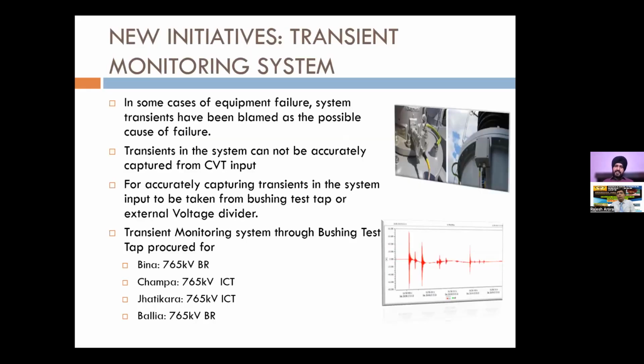Now, when we talk about initiatives in Power Grid, like I said, the high frequency transients are very much relevant. To monitor these transients, we have captured, and because these transients cannot be accurately measured through a CVT, because CVT is attuned for maximum accuracy of measurement at 50 hertz. So we have got this transient monitoring systems which are monitoring the system transients directly from bushing. Bushing basically acts as a voltage divider, and from bushing test tap, when you monitor, you can see a lot of transients at very high frequency.